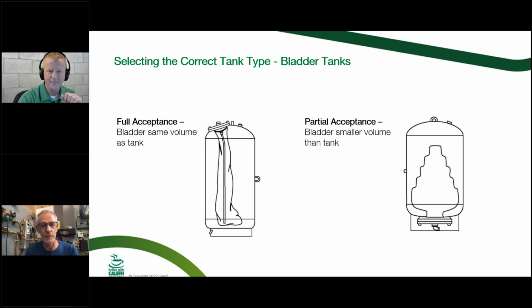Maybe that's a good rule of thumb, but I guess the bottom line is if an engineer designs a plan and he puts an ASME tank in there, that's what you want to use. If not, you can ask your inspector, your boiler code. I don't know where you're going to get an exact answer. And I think it could even come down to the actual inspector that shows up that day. He might have something in his head that says, oh, it's 118 gallons, you've got to have an, you know, I don't know. So I don't have an exact answer. You're going to have to check locally or check with an engineer in your area that does it for a living and knows what triggers an ASME requirement.